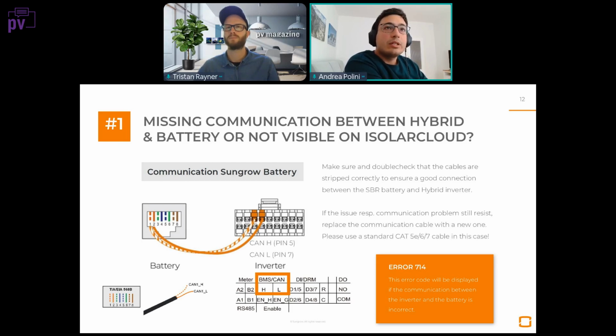It's very important that the cables are stripped and that no insulator is connected to the hole of the pin, because we usually had some problems with people not stripping the cables correctly. And if you want, you can also use cable terminations to put in the connector, but be sure that they are terminations with long enough tips that they can reach the inside of the connector. And the error that is shown is this error 714, when the connection is not correct between the inverter and battery.